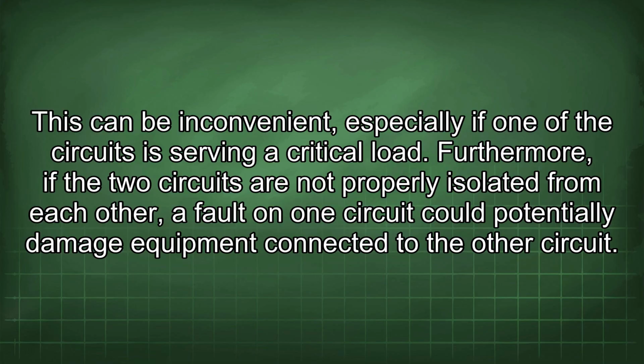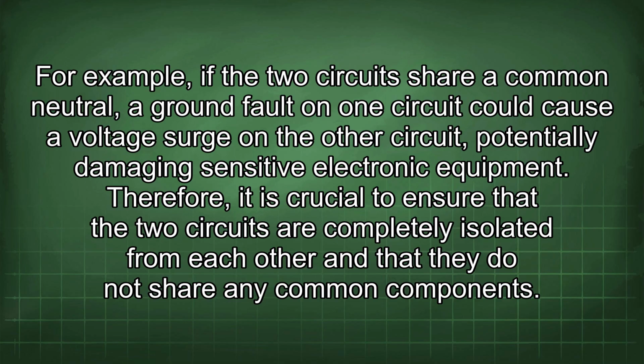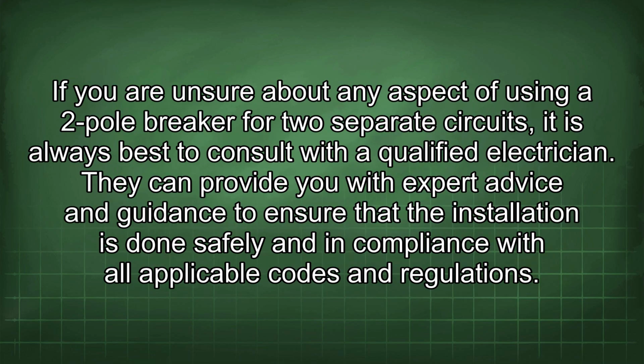Furthermore, if the two circuits are not properly isolated from each other, a fault on one circuit could potentially damage equipment connected to the other circuit. For example, if the two circuits share a common neutral, a ground fault on one circuit could cause a voltage surge on the other circuit, potentially damaging sensitive electronic equipment. Therefore, it is crucial to ensure that the two circuits are completely isolated from each other and that they do not share any common components. If you are unsure about any aspect of using a two-pole breaker for two separate circuits, it is always best to consult with a qualified electrician. They can provide you with expert advice and guidance to ensure that the installation is done safely and in compliance with all applicable codes and regulations.